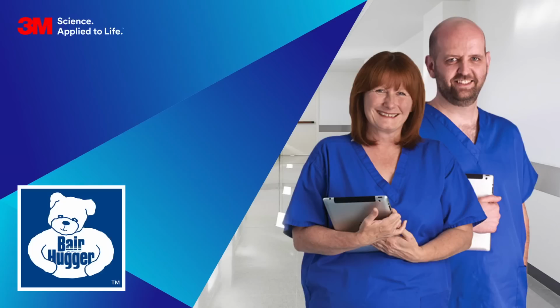Another question we got, Helen, was can we place a chest support on the surface of the full access underbody blanket model 635? You can place any kind of support in there. Ideally, you don't want to cover the whole of the blanket before you put your patient on it, because then you're occluding the airflow. But if you need supports, be it a lumbar support or a chest support, you can put that in. Ideally, you want to try and put it under the Bair Hugger, but I know in all cases that's not the optimum place for you. But as long as you've still got a good flow around it, yes, you can.